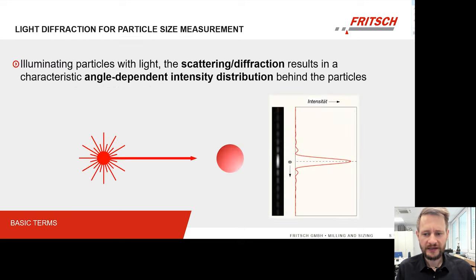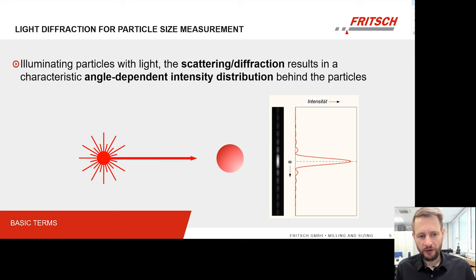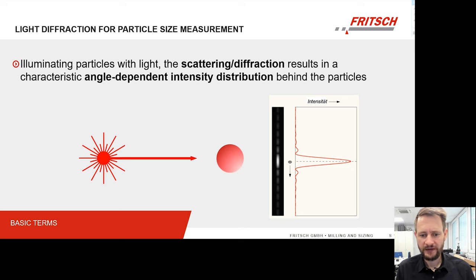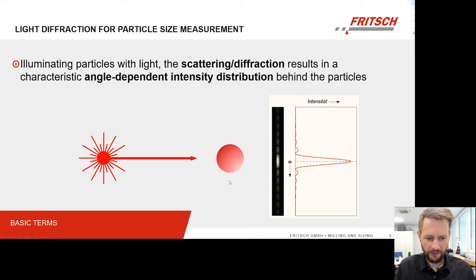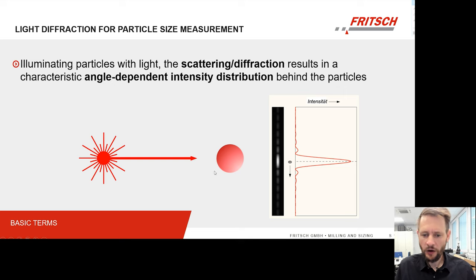It is called laser diffraction, which always gives us a hint at the physical process used to determine the particle size — it is light diffraction on our particles. As you can see here, we have a particle and from one side a laser source emitting laser light toward the particle, and on the other side a detector array. Without any particle in between, what we get on our detector is just one single peak from our laser beam. On the left and right side of that peak we have more or less darkness, so no signals.